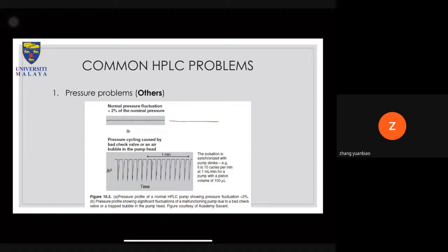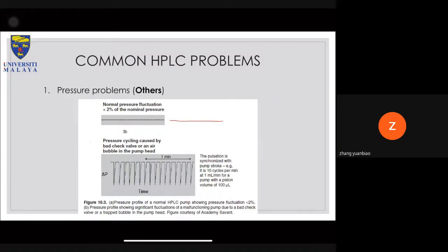Pressure cycling caused by a bad check valve or air bubbles in the pump head can also be something like this. So this one is a change in the pressure, and the pulsation is synchronized with the pump stroke. For example, if there are 10 cycles per minute at 1 mL per minute for a pump with a piston volume of 100 µL. So if you see a regular interval like this, then it's a good indicator that the pump is actually the main culprit.